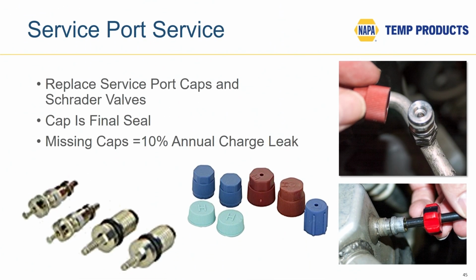Don't forget that the Schrader valve with the service cap is actually the final seal in the system. Generally, most air conditioning pro shops, as soon as they recover the refrigerant, before they even go to evacuate, replace the Schrader valve. I'm sure you've had the experience, I certainly have, where you put the whole system back together, charge it, disconnect the coupling, and are about to put the service cap on, only to find that the Schrader port is leaking. So it's just good practice to replace the Schrader valves as soon as you recover the refrigerant from the system.